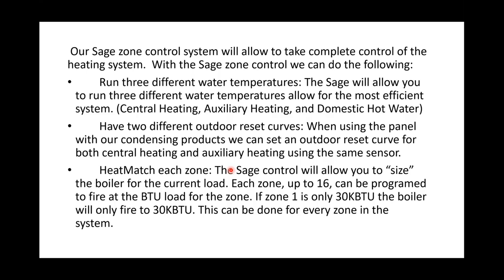It'll also allow us to run 3 different water temperatures with 2 different outdoor reset curves. I can have my domestic hot water temperature, a central heating temperature with its own reset curve, and an auxiliary heating setpoint with its own reset curve. If I was doing radiant with fan coil backups, or high temperature baseboard with panel rads, you can get really creative with it.